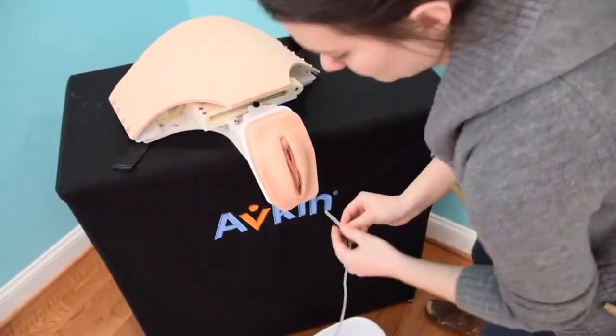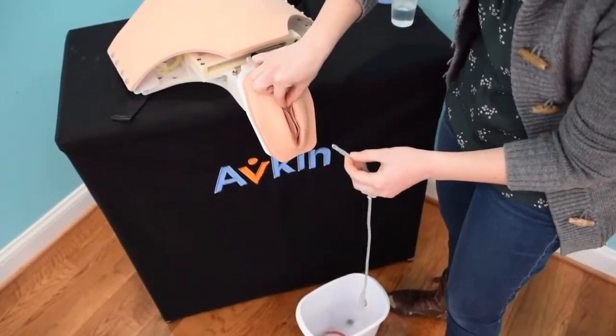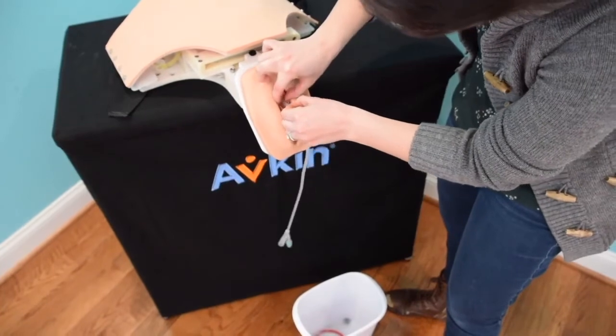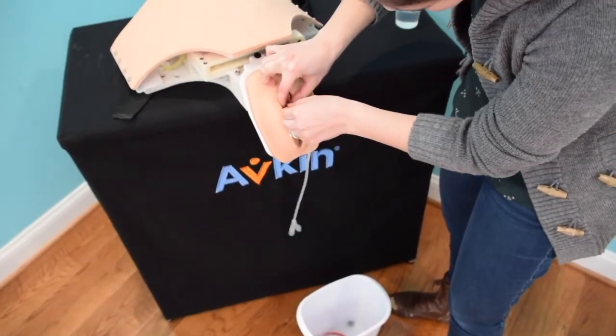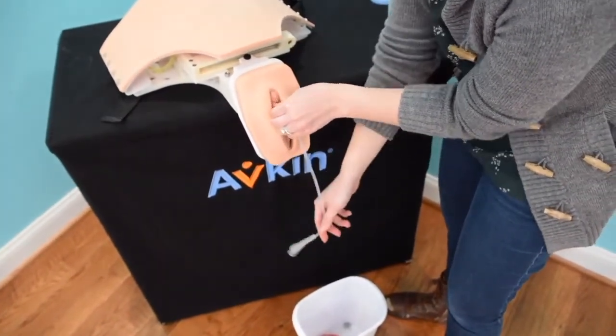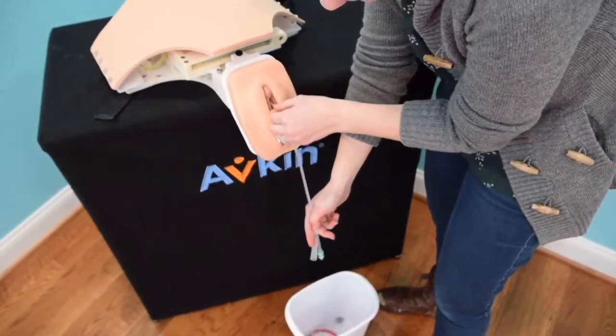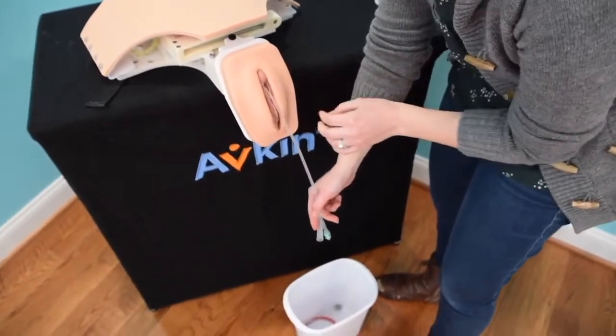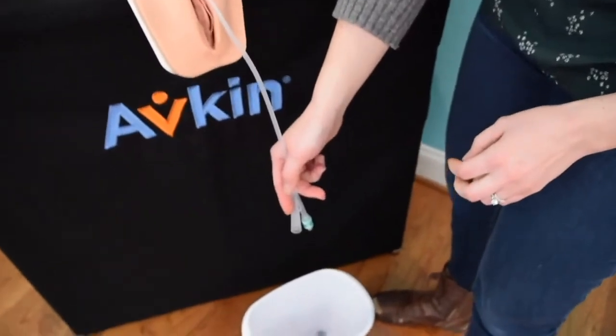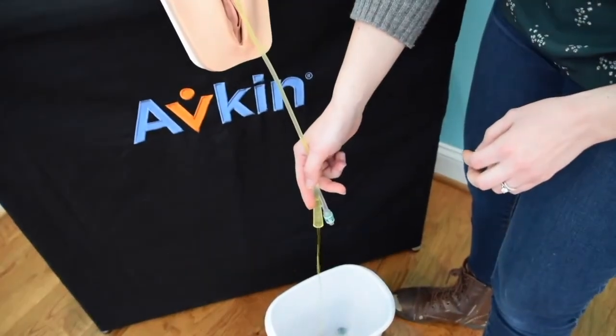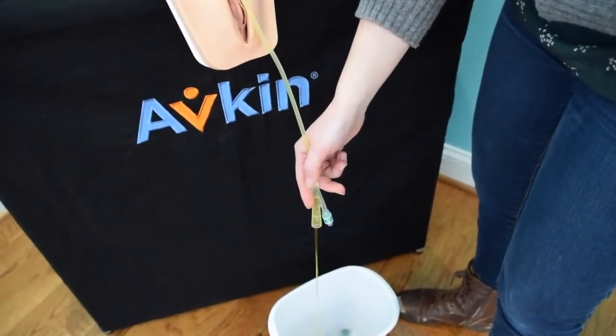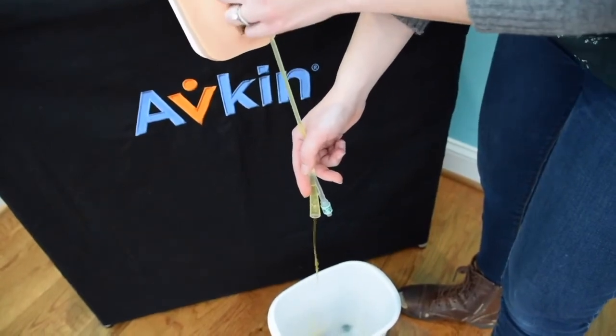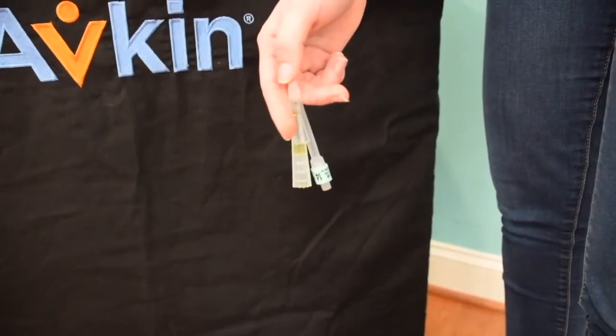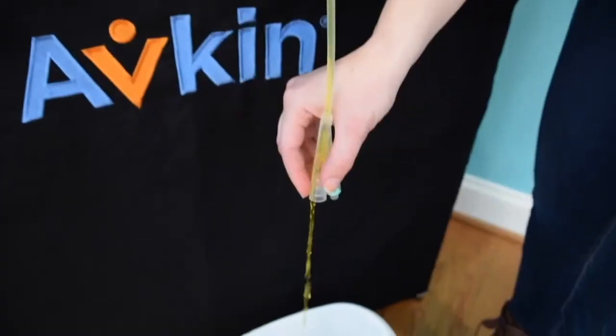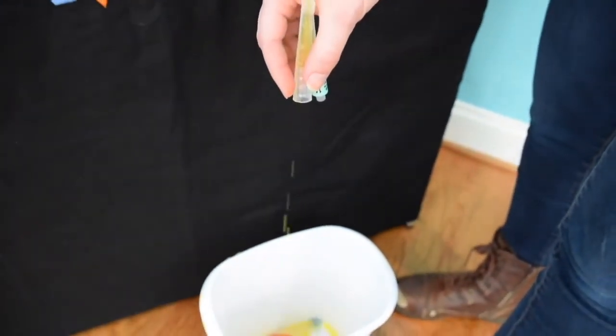While we still have the device off of our simulated participant, let's try putting a catheter in and make sure that we aren't getting any leaking and are able to insert the catheter easily. Take one of the catheters provided in the kit and put it inside the urethra. We are going to allow it to drain into an open container. If you detect leaking in your system coming out of the urethra around the catheter, you may need to replace the finger cot. Refer to our maintenance video for instructions on how to do this. If you are not able to progress your catheter far enough, you may need to put mineral oil in the urethra.